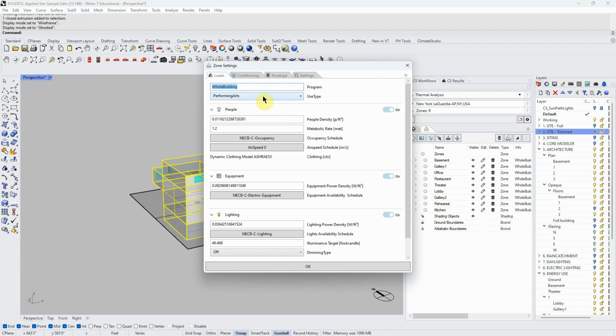They took a bunch of performing arts buildings from around the country, the United States, or a different country or organization, whatever. It doesn't matter. There's a group of buildings that were surveyed, and they separated them into different building types and created sort of a baseline average for a decent building, and then that EUI becomes the baseline, and then you're comparing yourself to that, right?